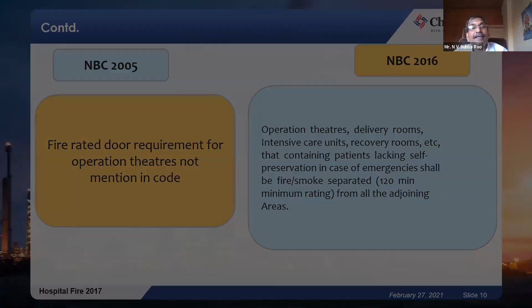The key element is that at design time, this standard should come into place, with various checks and balances. There's a concept called PSSR, pre-startup safety review, which hospitals can introduce before starting operations. If hospitals do this, they know how much the design considerations have taken fire safety aspects into account, and how far the designer, architect, and others have met requirements—what gaps exist, and what can be done before starting full-time operations.